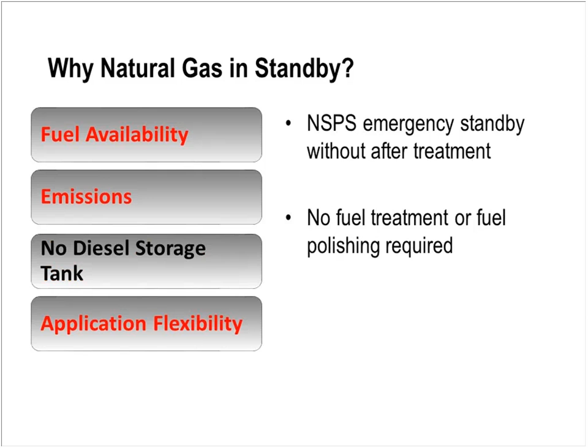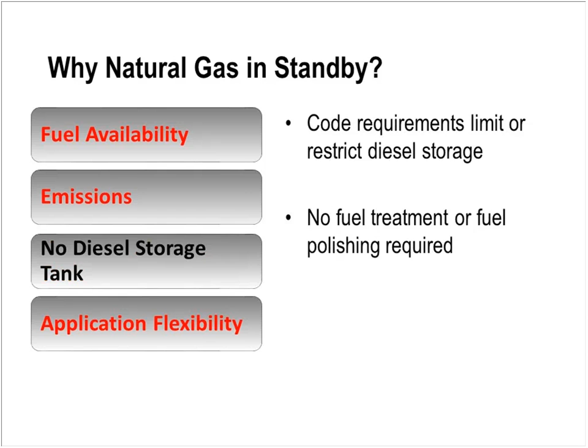But for true standby applications, a lot of these are working quite well. With diesel fuel tanks, there are code restrictions in many coastal or flood-prone areas—and it doesn't have to be coastal. Looking at the Mississippi, and what happened in Iowa and Missouri about 10 years ago with all the flooding challenges there—many of those areas are restricting the amount of diesel fuel that can be located in flood-prone areas. With gas, there's no fuel polishing required.